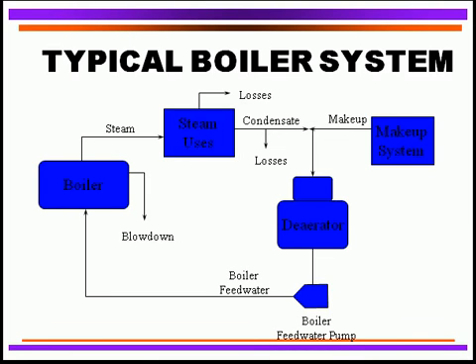A typical boiler water system is basically almost a closed water system. The only losses you ever have from a typical boiler system is where we lose some steam and where we actually get some blow down from the boiler. If you can minimize both of those, you are basically almost a completely closed system.